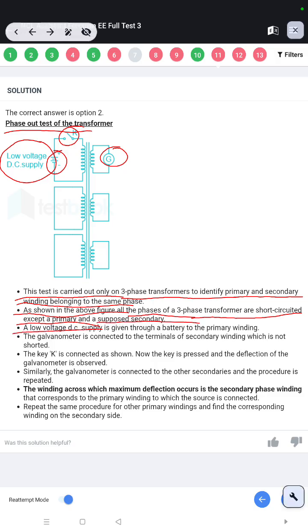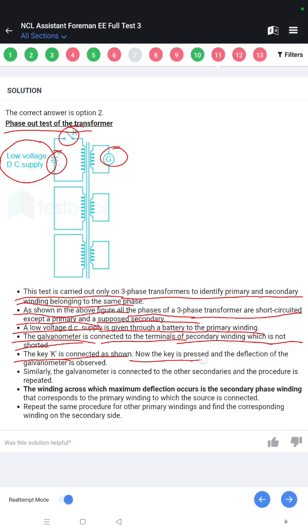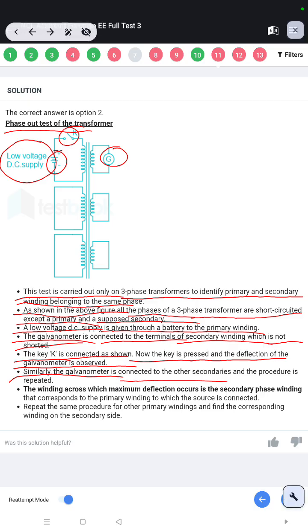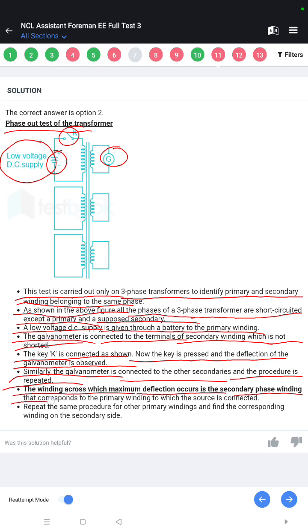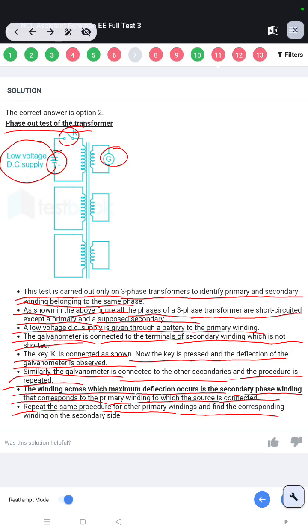A low-voltage DC supply is given through a battery to the primary winding. The galvanometer is connected to the terminals of the secondary winding which is not shorted. The key K is connected as shown. Now the key is pressed and the deflection of the galvanometer is observed. Similarly, the galvanometer is connected to the other secondaries and the procedure is repeated. The winding across which maximum deflection occurs is the secondary phase winding that corresponds to the primary winding to which the source is connected. Repeat the same procedure for other primary windings and find the corresponding winding on the secondary side.